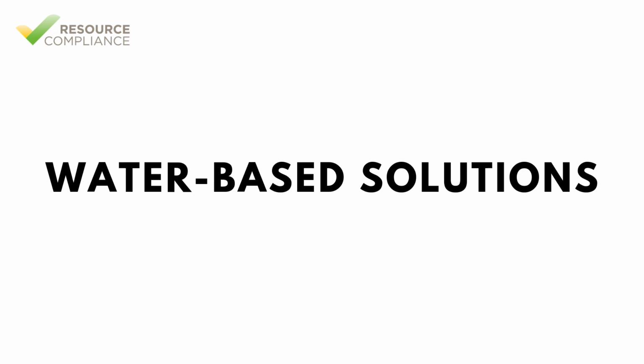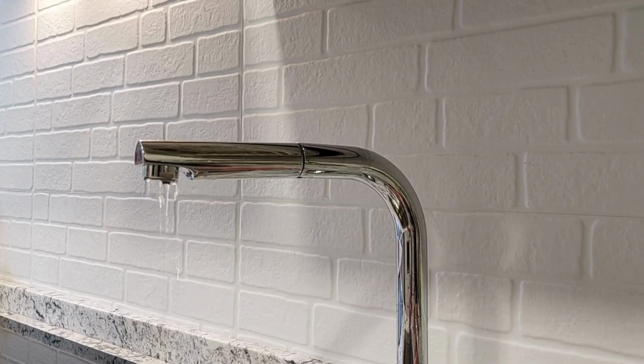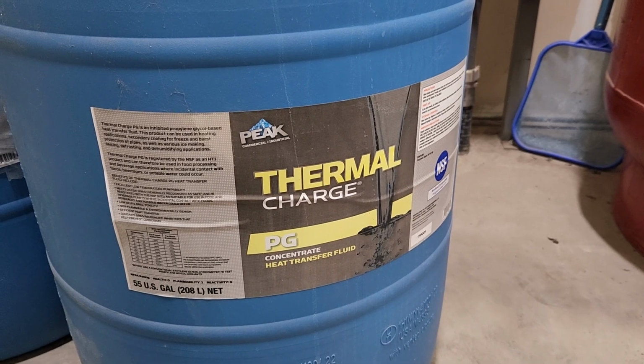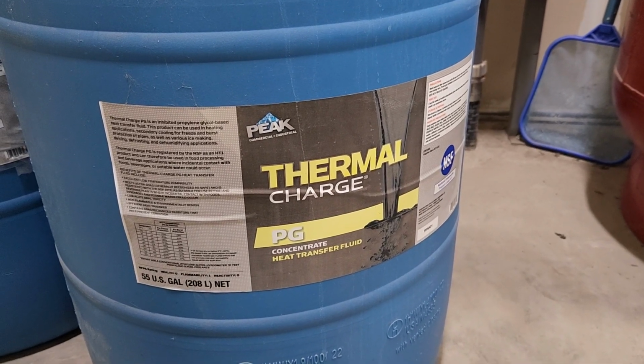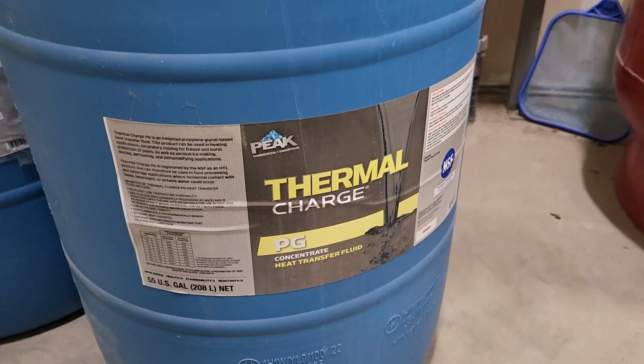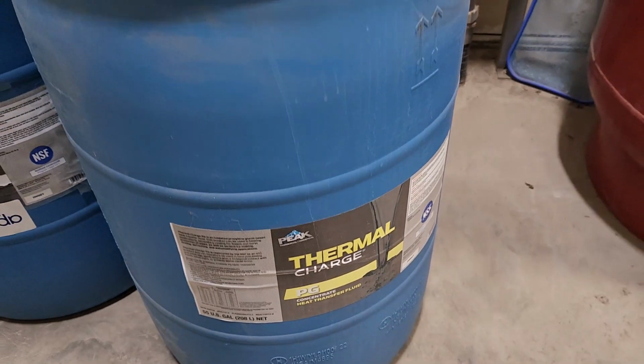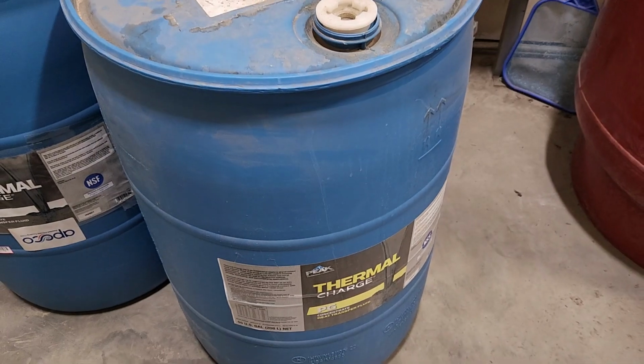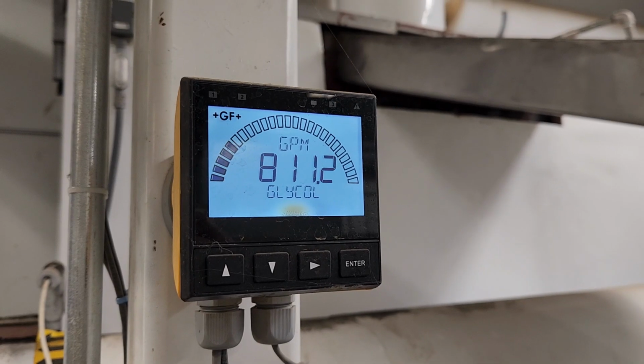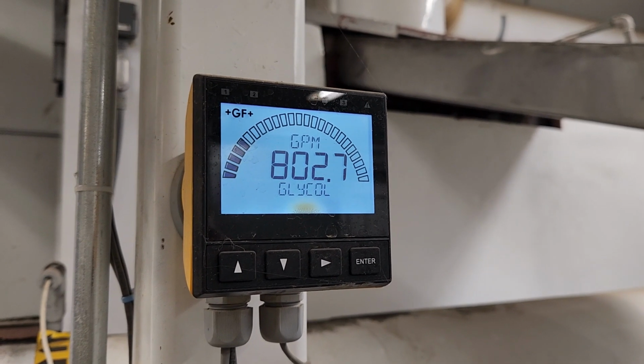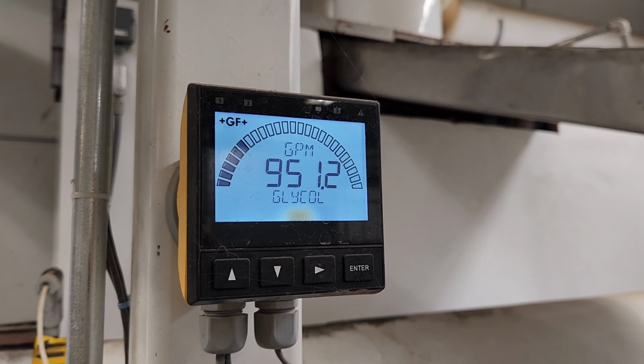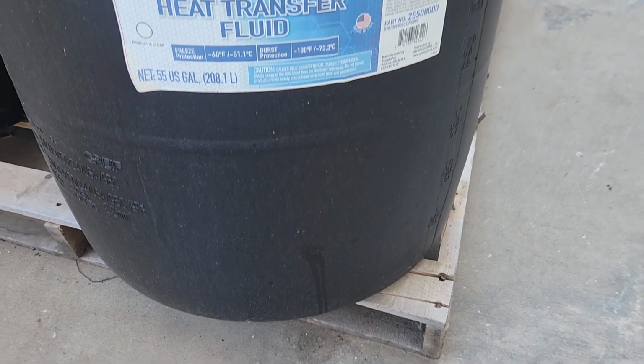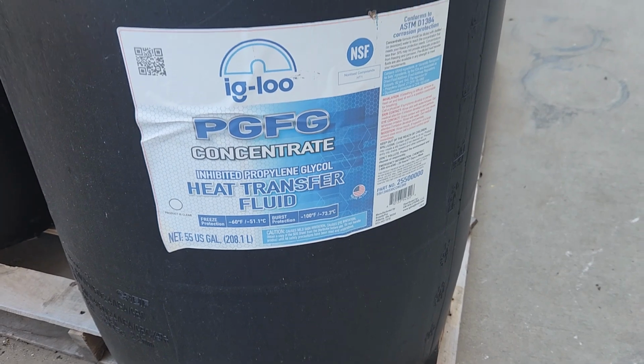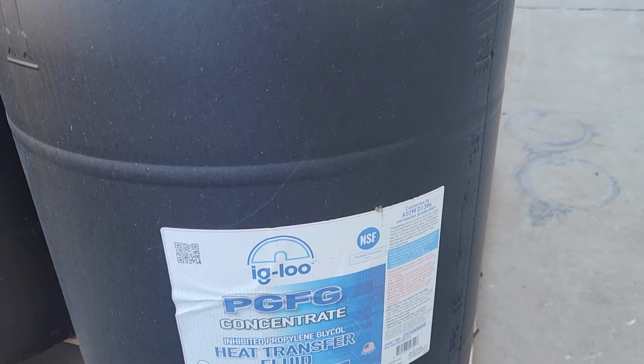There are many types of secondary coolants. Water is most commonly used as a secondary coolant due to its excellent heat transfer properties. However, because of its relatively high freezing point, it is often mixed with additives such as ethylene glycol or propylene glycol to prevent freezing and corrosion in low temperature applications. Ethylene glycol is toxic and therefore cannot be used in facilities that handle food or beverages. Water glycol mixtures are common in HVAC systems and other refrigeration applications.